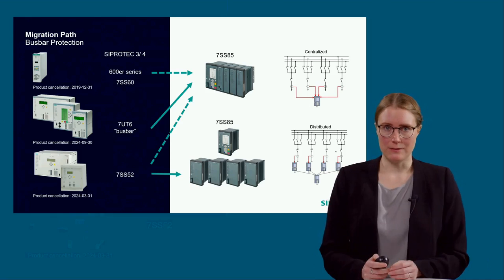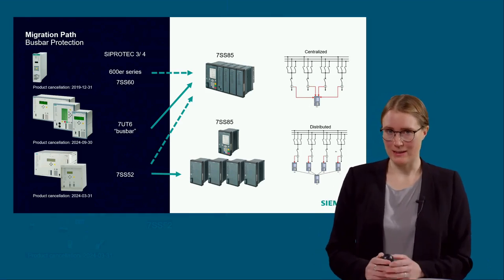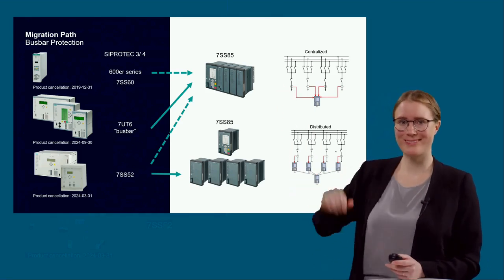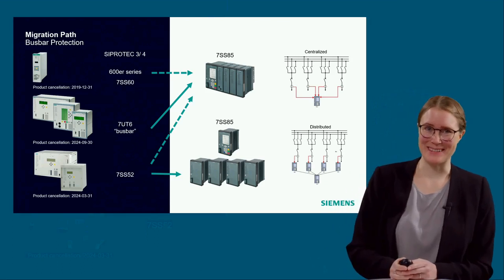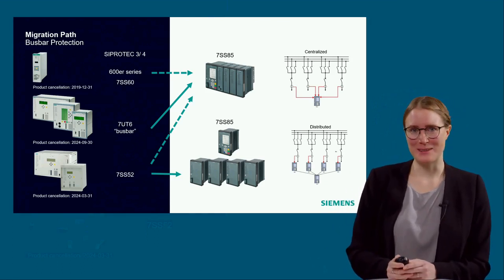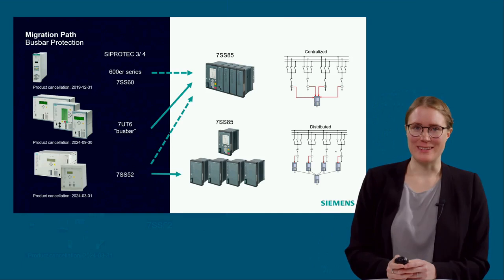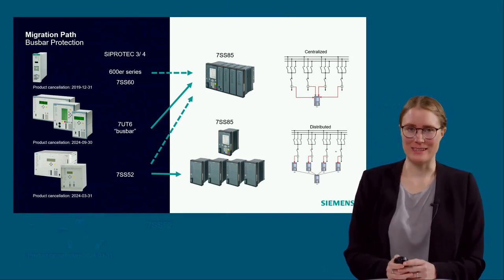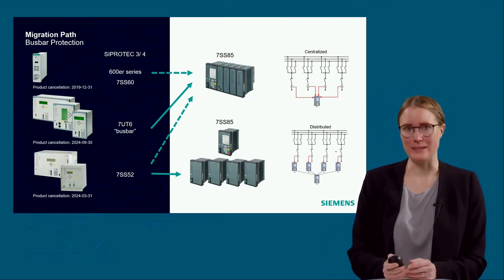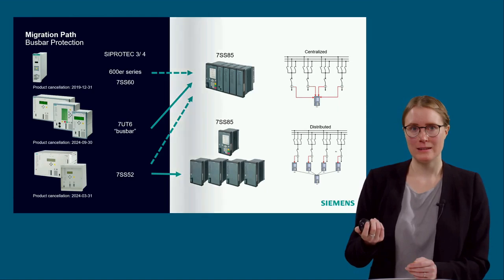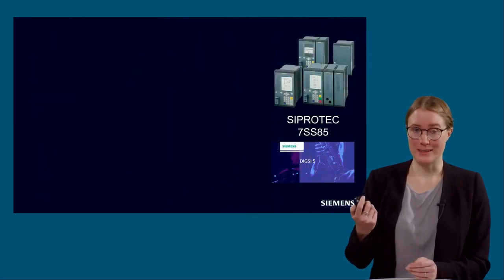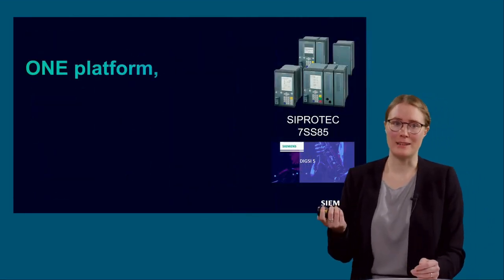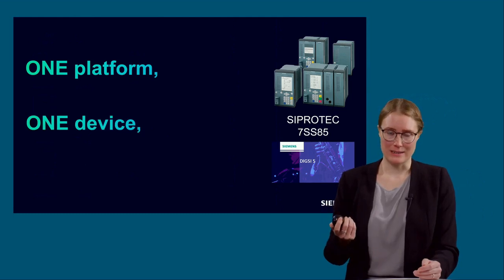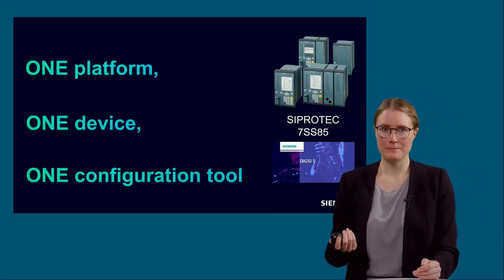The 7SS85 can be used in a centralized approach or in a distributed setup. For the distributed solution, as bay units you can use every SIPROTEC 5 protection device or, of course, the 6MU85 as merging unit in the feeder. So in SIPROTEC 5, we have one platform, one device, and one configuration tool.